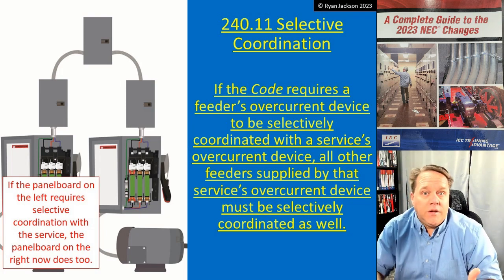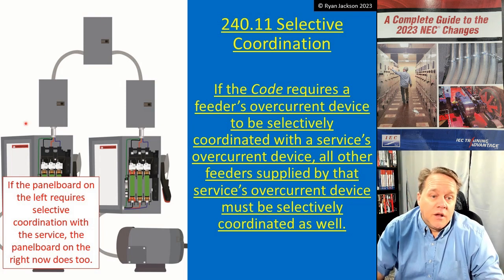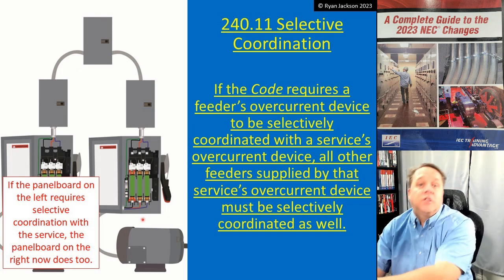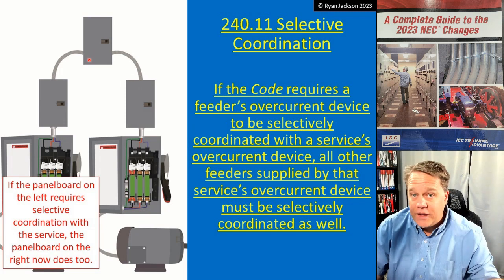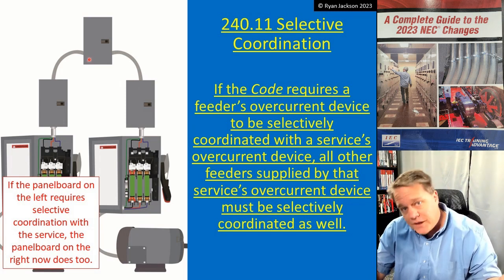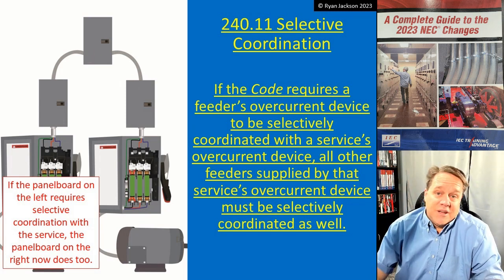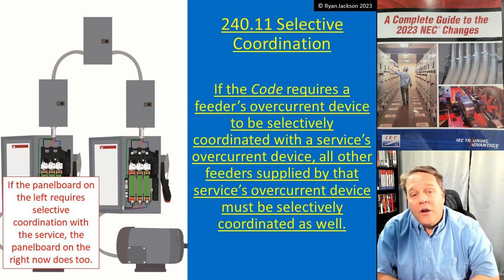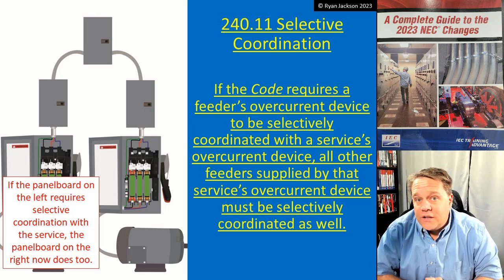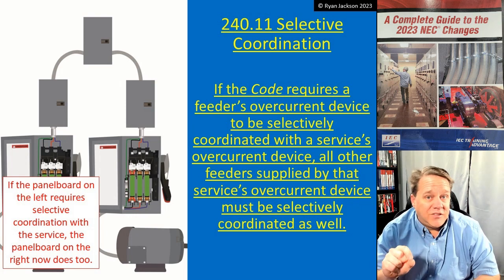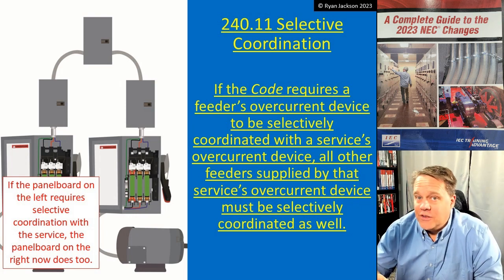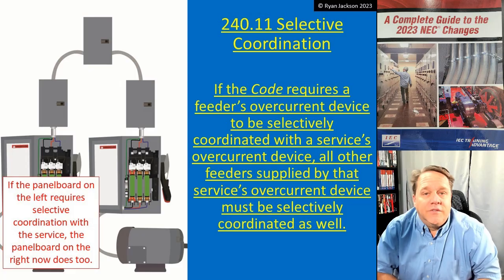There's no point in selectively coordinating the left half of a building if one fault on the right half can knock out everything on the left. It's something maybe we didn't think about in previous versions of the code. So there you go - 240.11 selective coordination. This has the potential to be a big deal if you're in the design world.